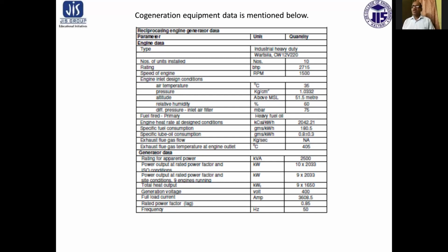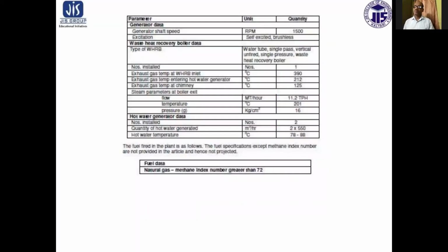Generator data, ratings for apparent power that is 2500, power output at rated power factor that is given 10 into 2033 kilowatt, power output at rated power factor site condition 9 engines running at 9 into 2033, and total heat output, that is 9 into 1650. Generation voltage 400, full load current is 3608.5, power factor 0.85, frequency 50 Hz. Generator shaft speed, that is 1500, excitation self excitation brushless.